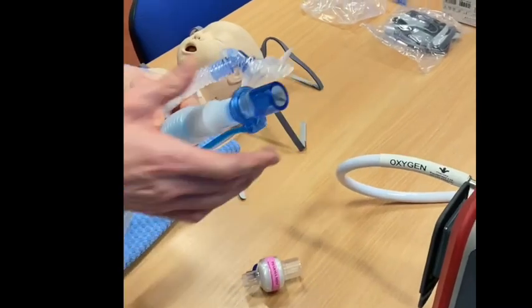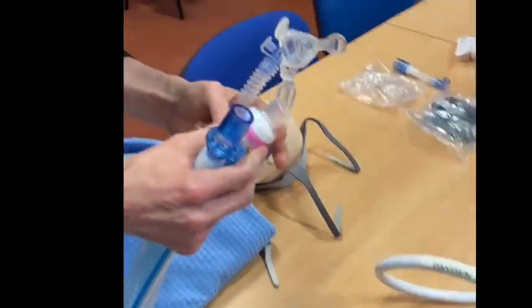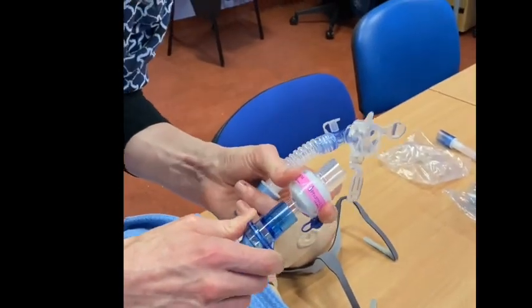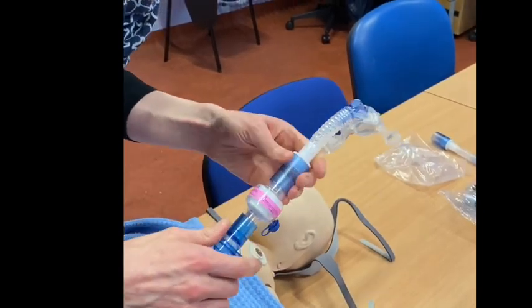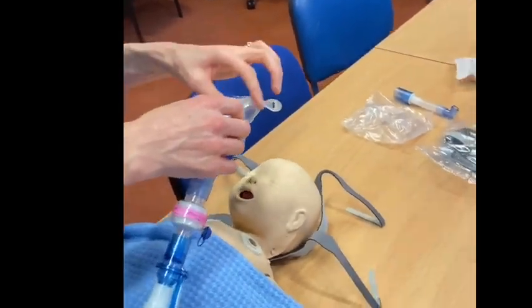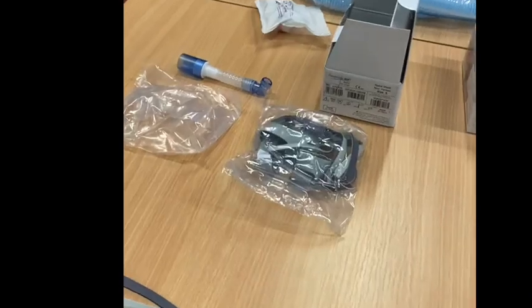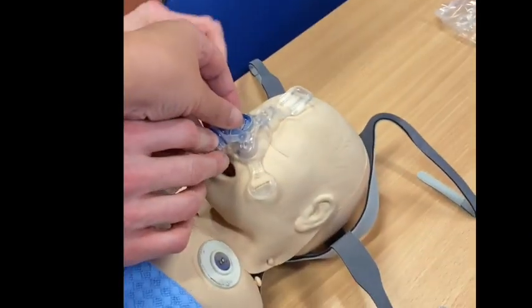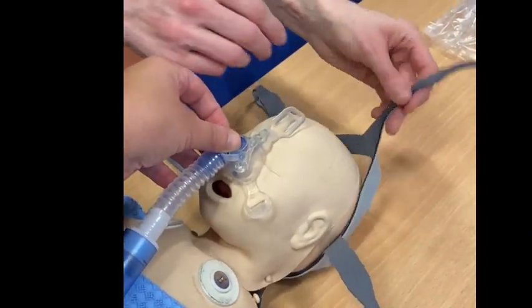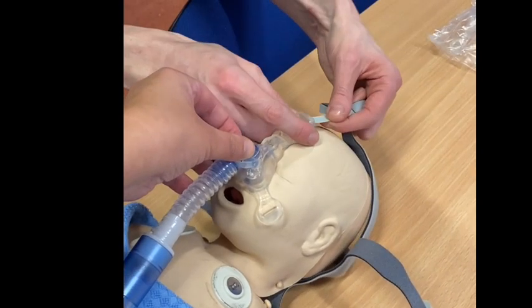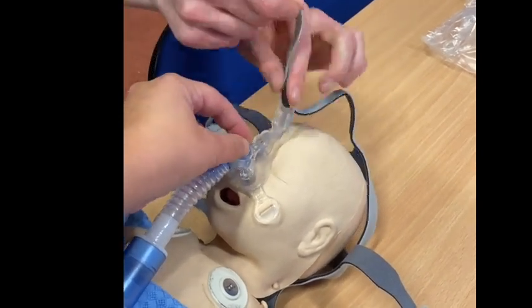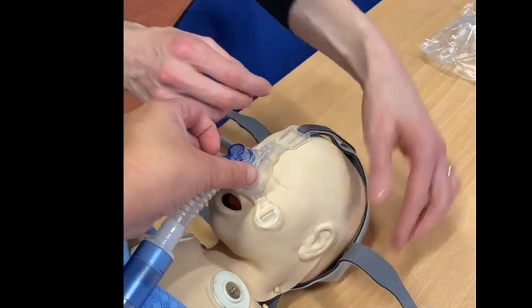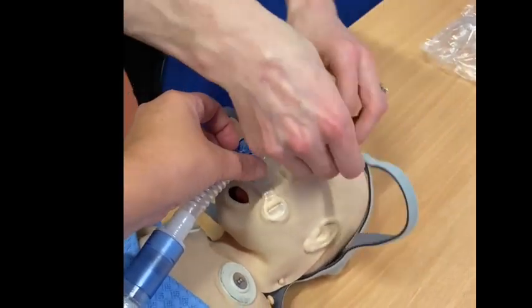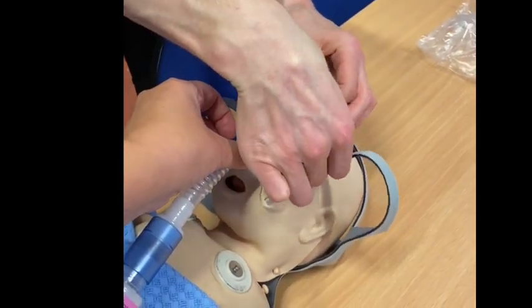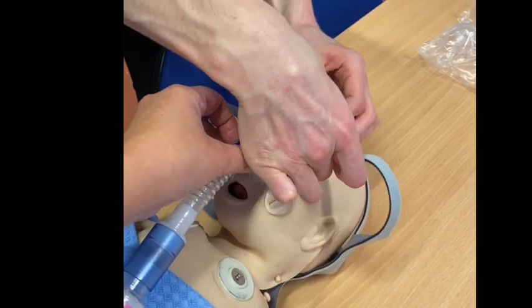To connect your tubing, insert your HME onto the coaxial circuit, and then simply insert the CPAP vent tubing onto that. Ask an assistant to hold the mask over the baby's nose and start the flow of oxygen via the ventilator as you then secure the strapping. These straps have quite long extensions with significant area for Velcro attachment that allow for quite a large variation in head size.